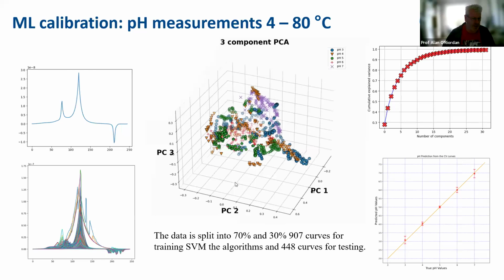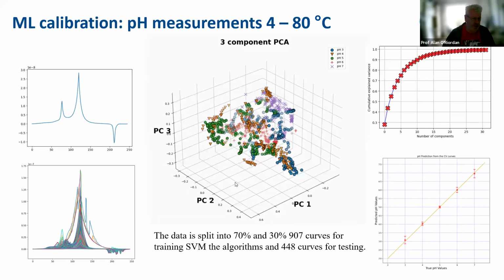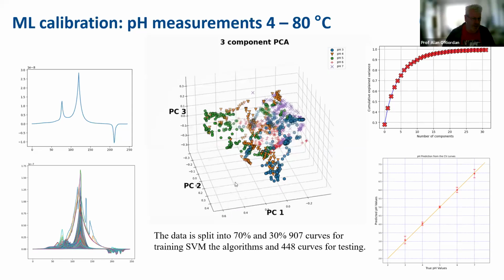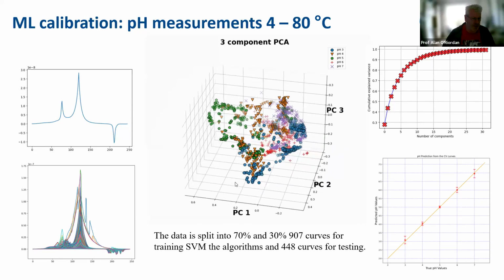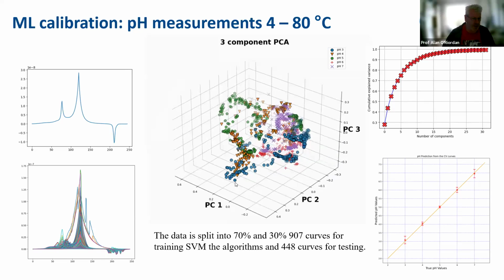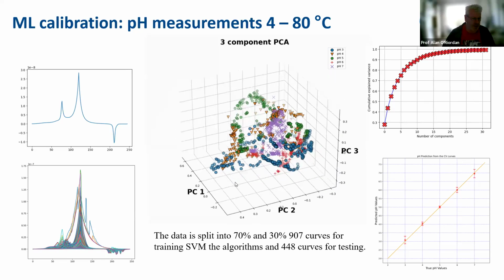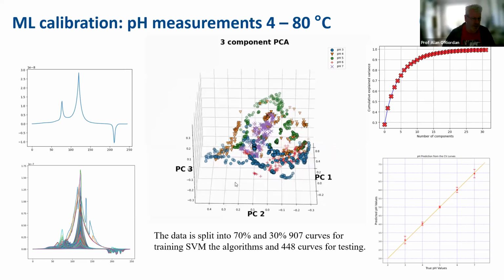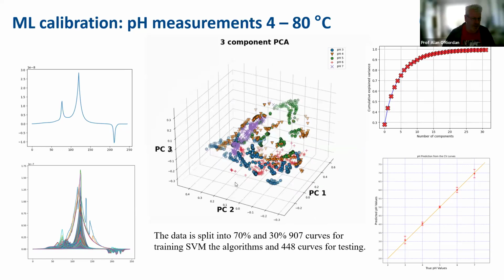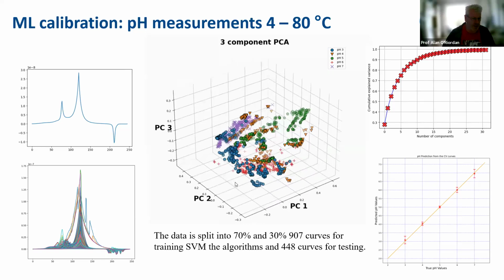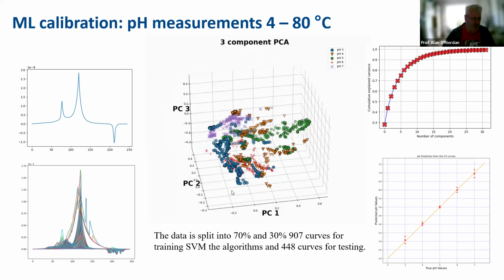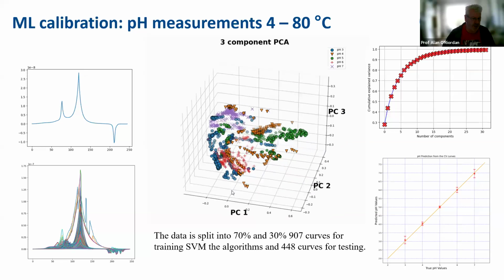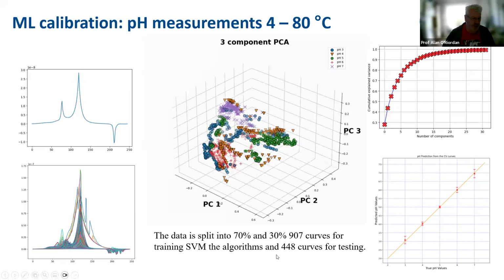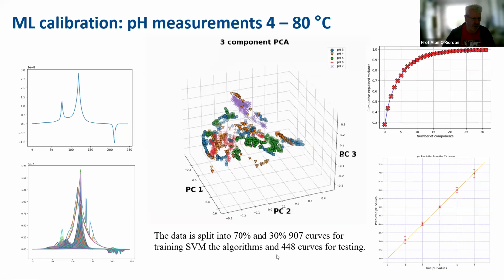So finally, as well, I mentioned earlier the challenges around calibration and the slight variations that fabrication gives you. One of the approaches that we're using now to address that is to use different machine learning tools to build up a model of all the different types of CVs or square waves that we get, and then using either spiking neural networks or, in this case, principal component analysis to build a calibration model. This example here is for pH measurements, so identifying where that reduction peak is.